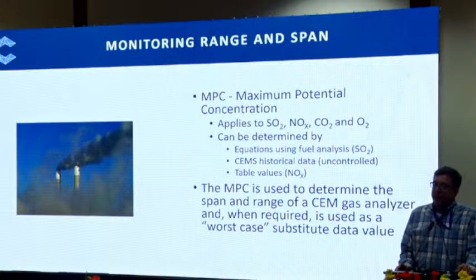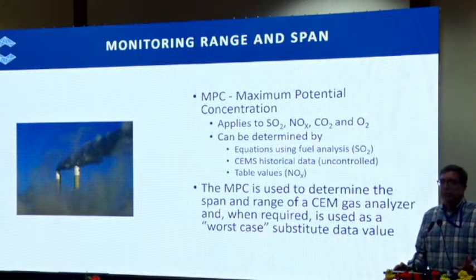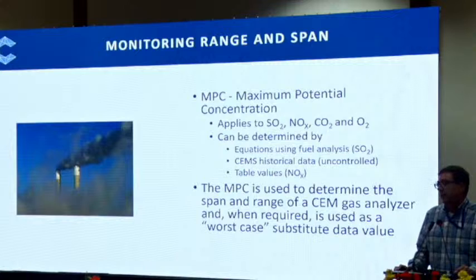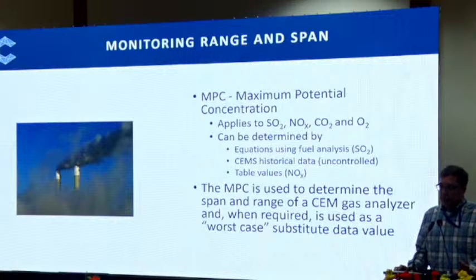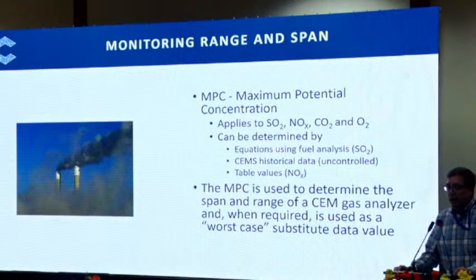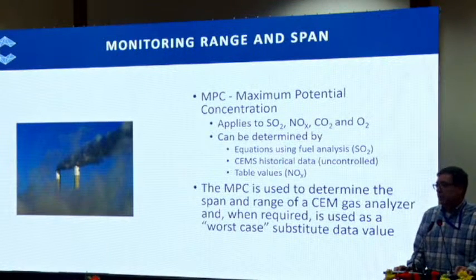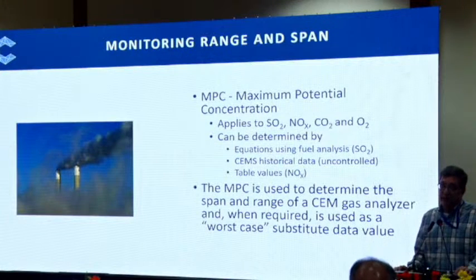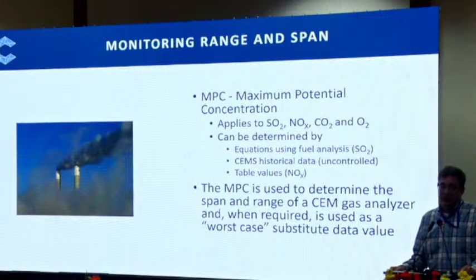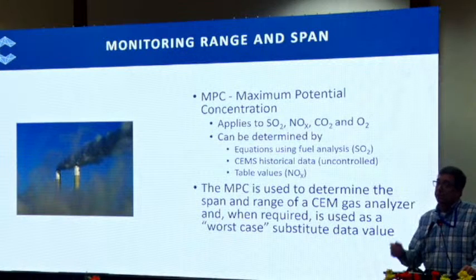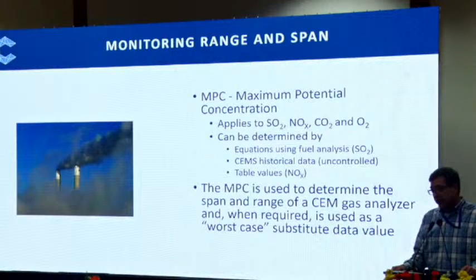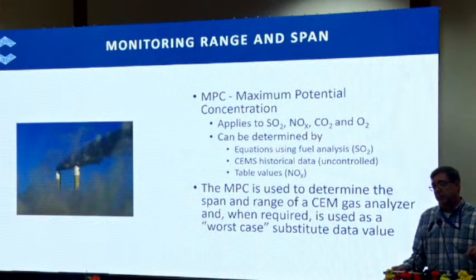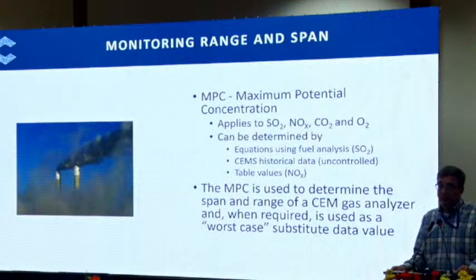So, establishing a monitor range and span. This is very prescriptive according to Part 75 in the US EPA. Your maximum potential concentration applies to SO2, NOx, CO2, and O2. Now, you can determine this either by using equations from fuel analysis, for SO2 for example, or CEMS historical data from uncontrolled sections. So if you were to install an FGD on your facility, you should be able to go back and look at your previous historical CEMS data where you weren't controlling, and you could derive maybe a maximum potential concentration off of that over years of data.